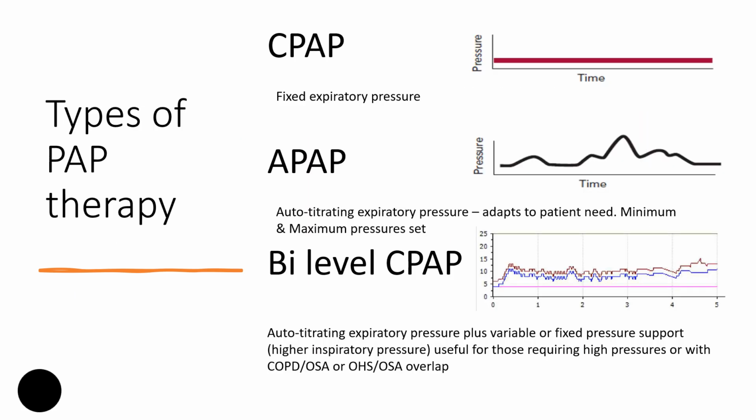So I mentioned CPAP, but actually we have different types of what we call PAP therapy, so positive airway pressure therapy. So CPAP usually refers to continuous pressure, where the pressure the machine's delivering is just the same pressure over the entire night. We often also use something called APAP, so auto titrating, where the machine's constantly adjusting itself to find the right pressure to what you need.